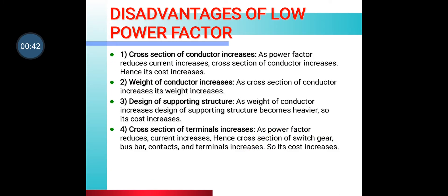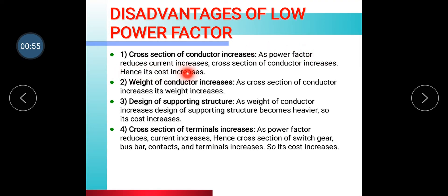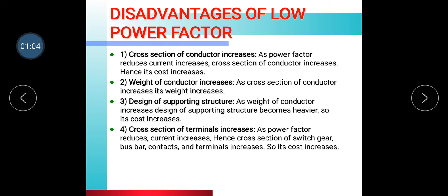Now, the disadvantages of low power factor. The first disadvantage is that the cross section of conductor increases as power factor reduces. As power factor reduces, current increases, so the cross section of conductor increases, and hence its cost increases.